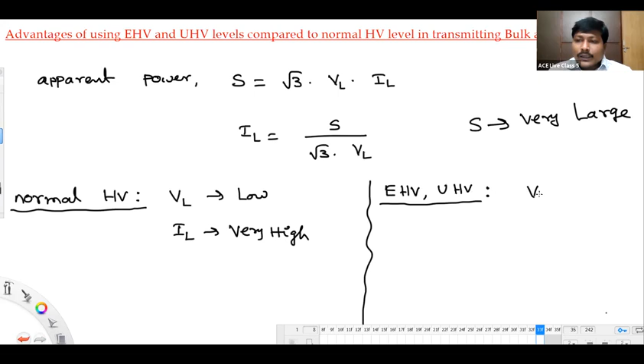Next, I will write here: EHV and UHV levels, maybe 220 kV, 400 kV or 765 kV levels. Here we are expecting a high line-to-line voltage number. If the line-to-line voltage is very high, definitely IL comes out very low. So the line current will be very, very low.